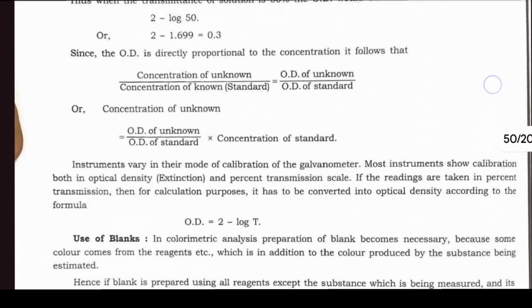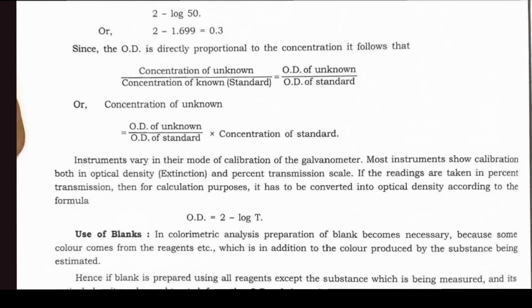Instruments vary in their mode of calibration of the galvanometer. Most instruments show calibration both in optical density, extinctions, and percentage transmission scale. If the readings are taken in percent transmission, then for calculation purpose, it has to be converted into optical density according to the formula.